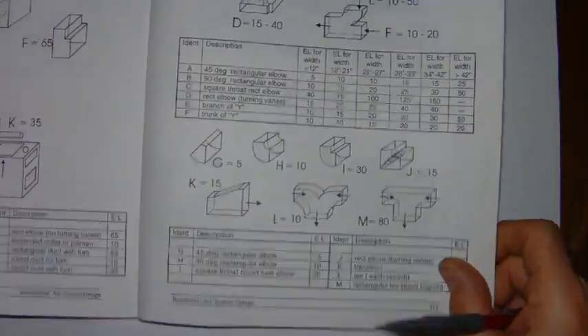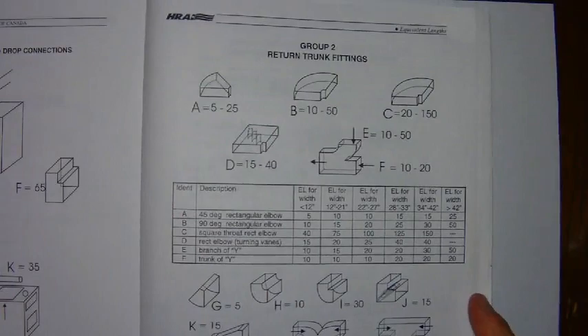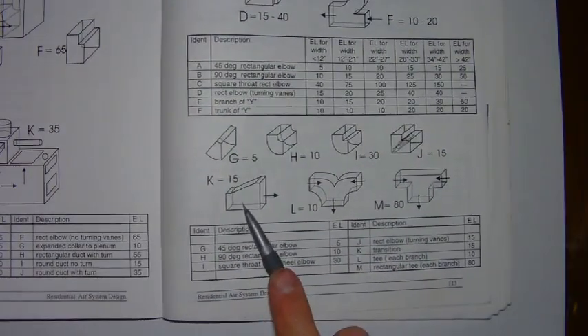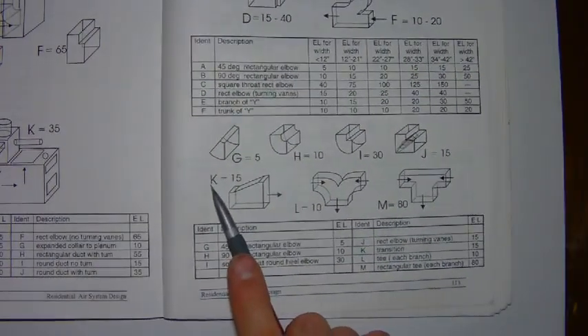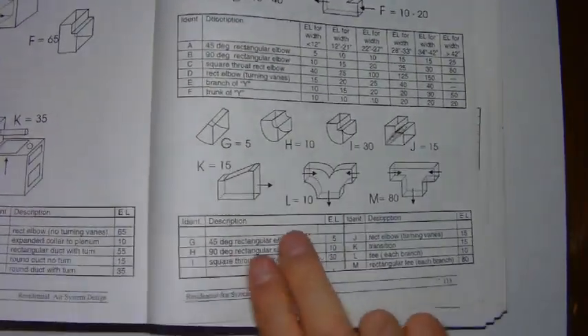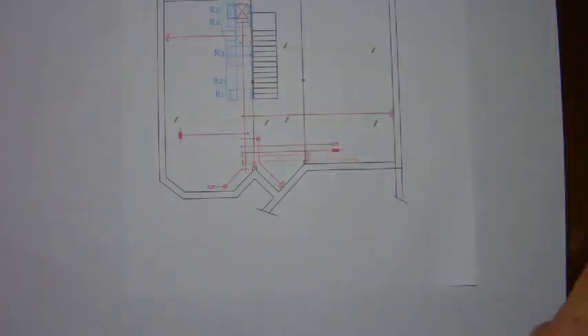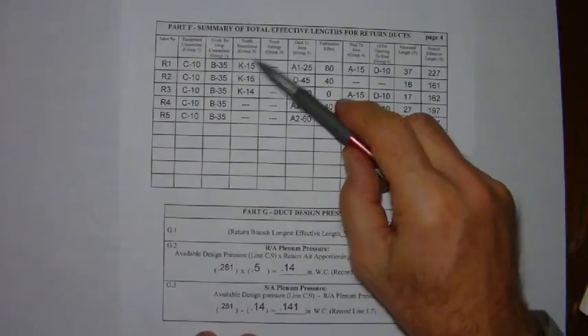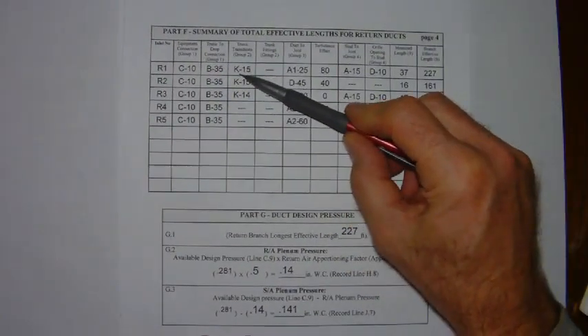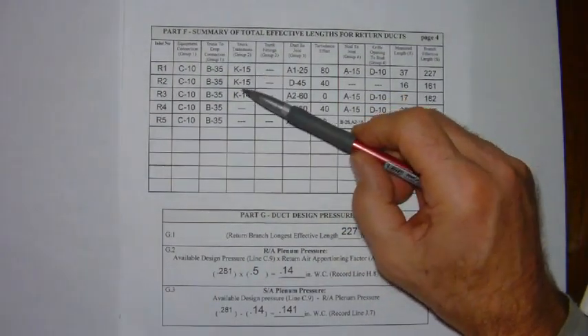And so when you look at the group two fittings, you'll see the transition is indicated as a K fitting and it is associated with 15 feet of equivalent length. Therefore run number one will have the K fitting with 15 feet.